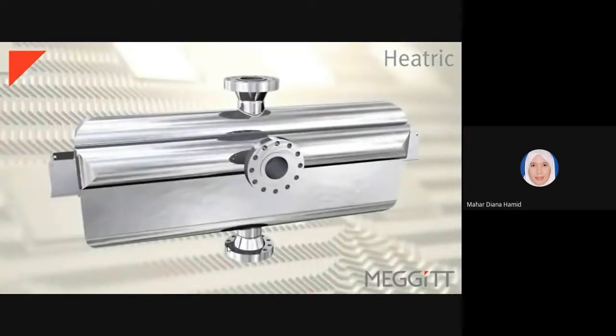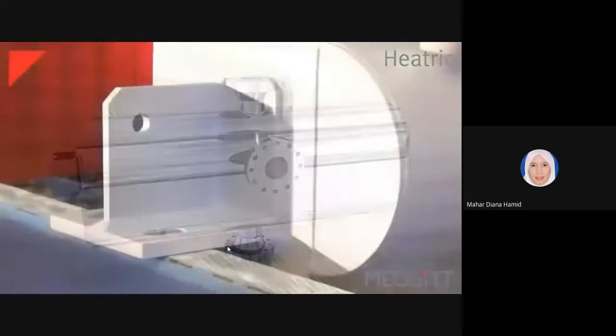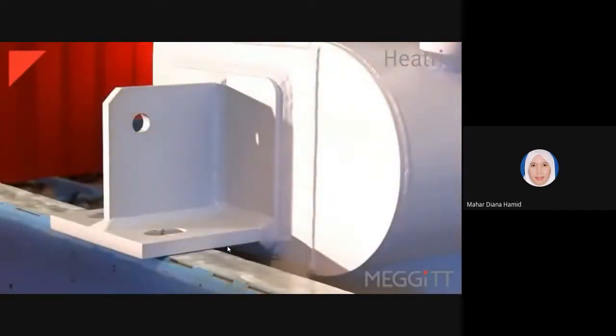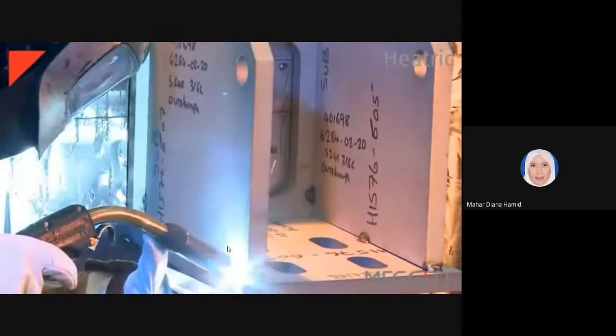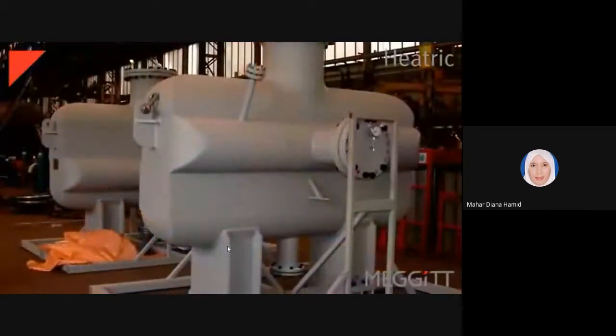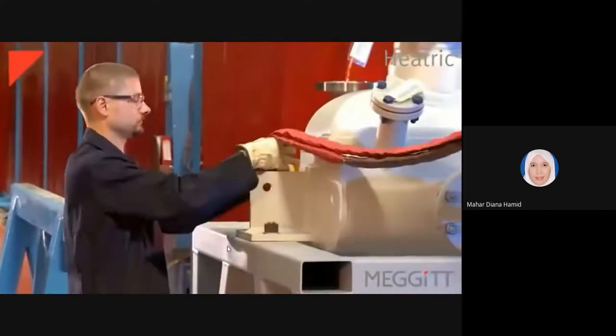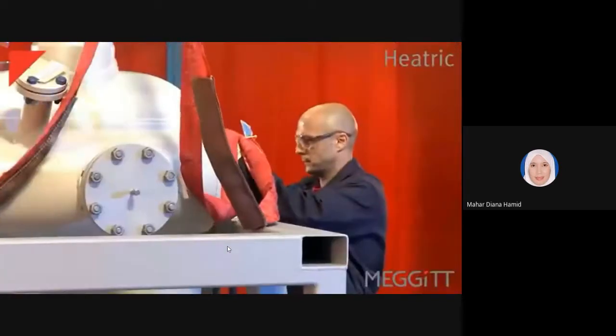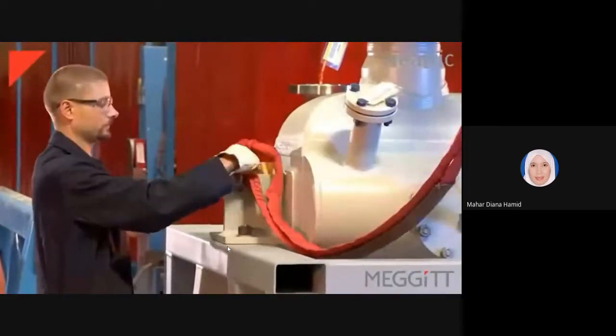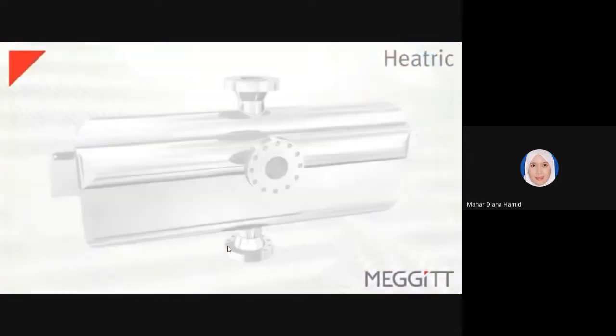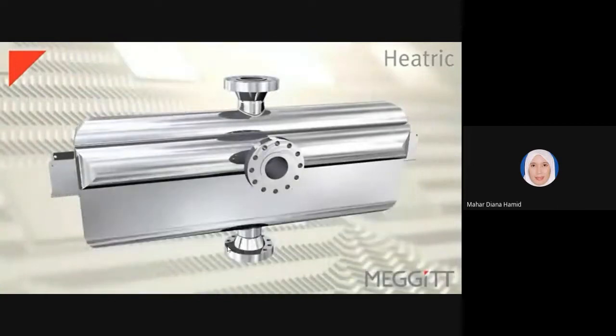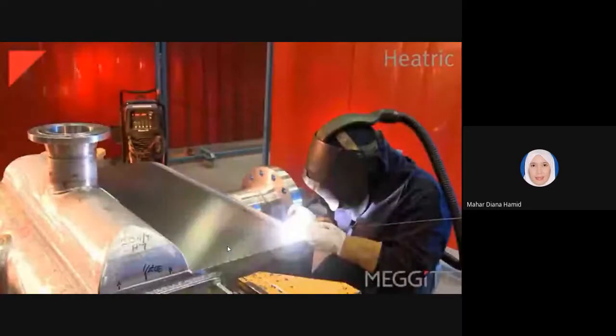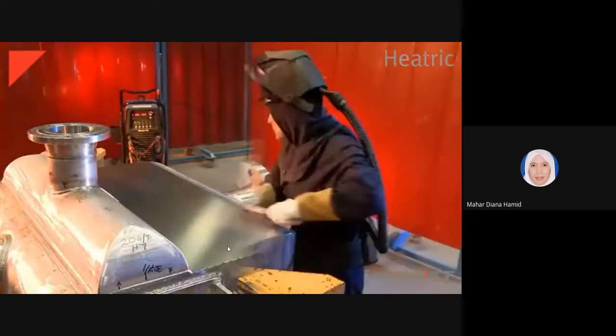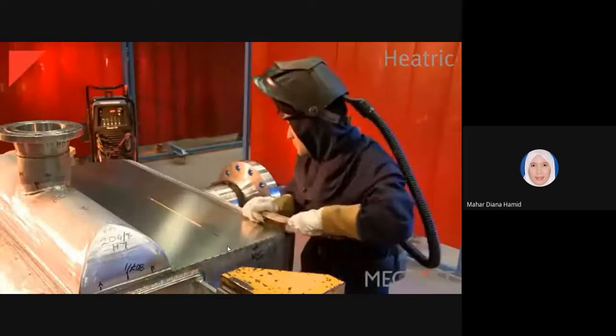Supports are then attached to the exchanger. The most widely used method is the N-type support. These are welded to the ends of the exchanger core. Alternatively, saddle-type supports can be fitted to the lower header of the exchanger. Lifting lugs are typically located at each end of the exchanger and are suitable for fitting with D-shackles for the attachment of lifting screws and chains. The lifting points can be incorporated into the N-type supports. Finally, the exchanger can be externally protected by painting or by sheathing with a corrosion-resistant material. This sheathing is a sheet metal cladding that is applied to the outer surface of stainless steel cores for enhanced protection in marine environments, typical of offshore installations.